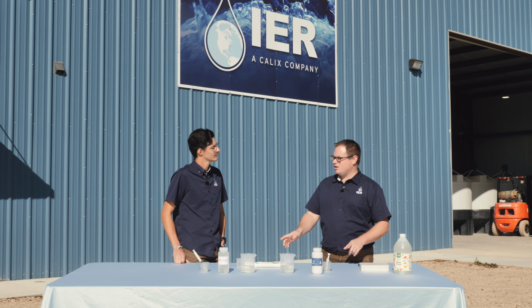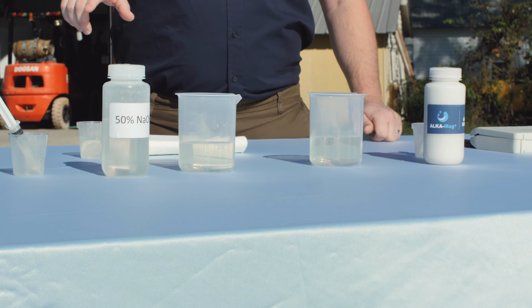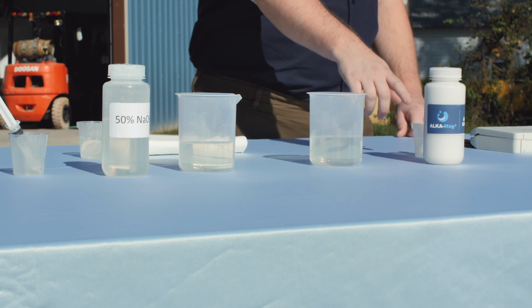The reason for that is stoichiometry. When you do all the fancy chemistry calculations, for every gallon or every mil of 50% caustic soda, we only need 0.6 gallons or mils of the magnesium hydroxide. So it's a 1 to 0.6 ratio, meaning 40% less magnesium hydroxide needed. So we want to show that.